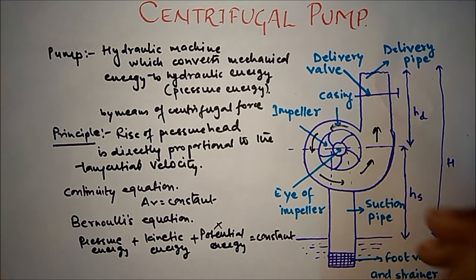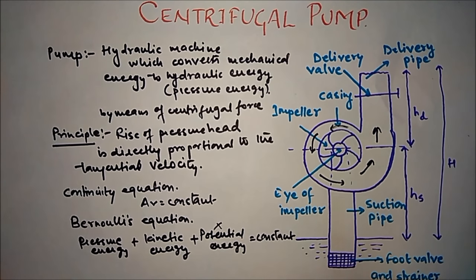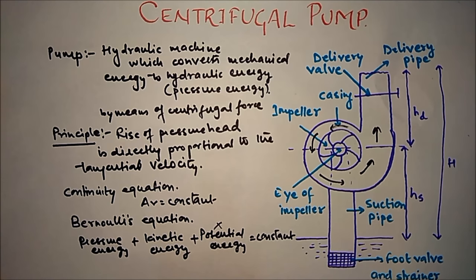Here, as the area increases, velocity decreases, so kinetic energy decreases. When kinetic energy decreases, pressure energy increases. So at the delivery pipe, kinetic energy is very low and pressure energy is very high, which ultimately increases the pressure head of the water — with the help of which we can take water from one point to another for our uses. The delivery valve is connected here to protect water from backflow.